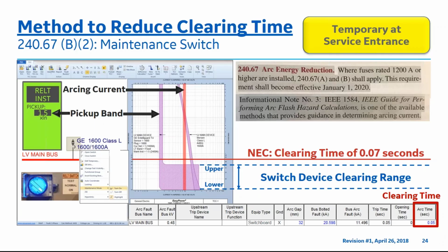At the bottom right-hand corner of the screen, the 0.05 second clearing time is shown as the arcing current clearing time for this fused application. On the left-hand side of the screen, notice the device settings for the maintenance mode for reduced energy let-through is turned on at 1.5 with a pickup band value, with the blue LED switch activated just below the green screen on the left-hand side. Remote activation is possible as well.